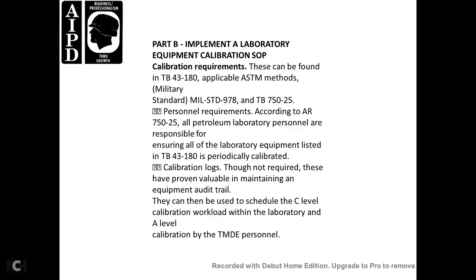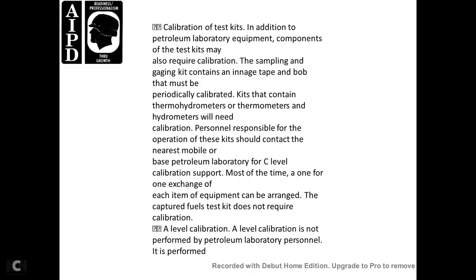Calibration logs. They are not required, but they have been valuable in maintaining an equipment audit trail. They can also be used to schedule the C-level calibration workload with the laboratory and the A-level calibration of the TMDE. Calibration and testing equipment.